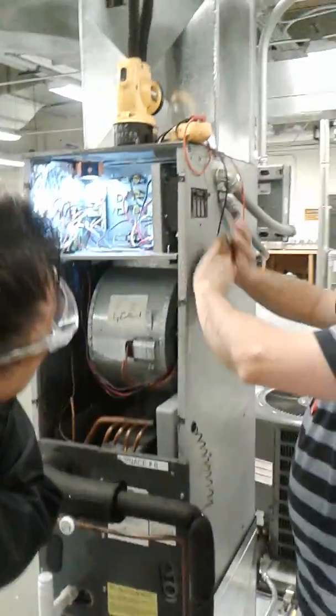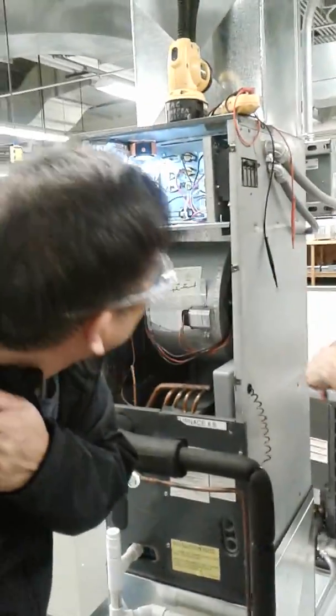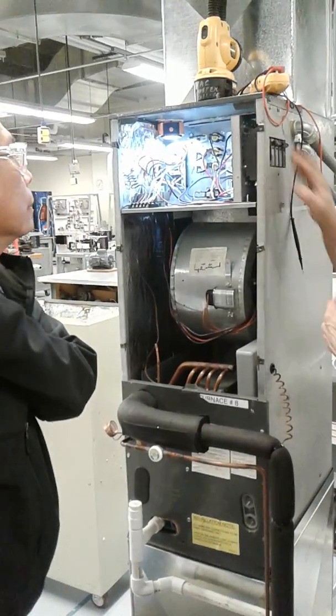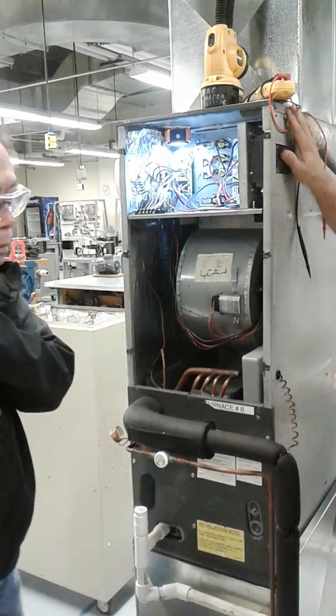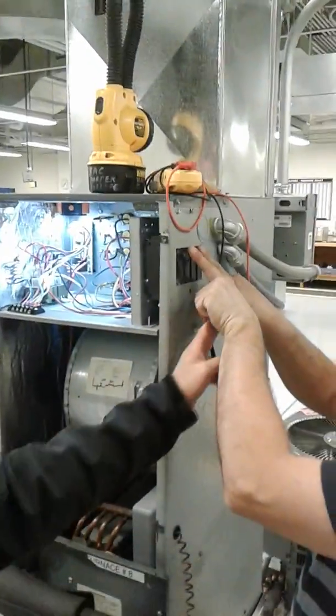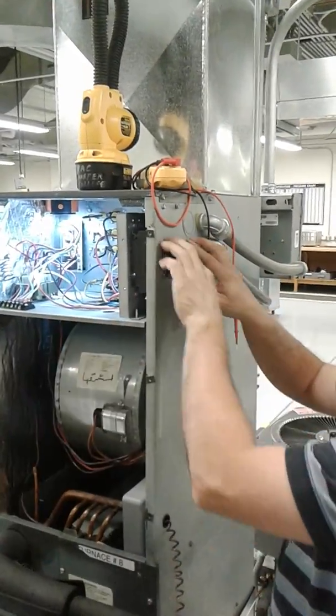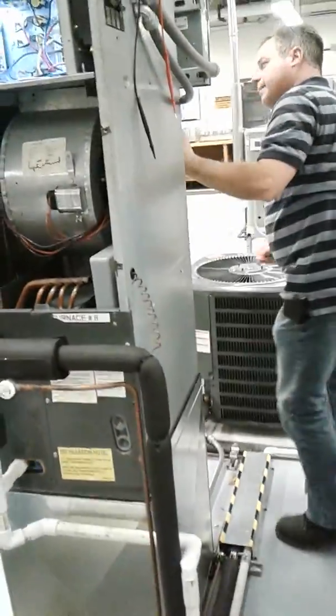Energizes the furnace. That's it. There's no gas valve. There's no other source of power except for the breaker right here. Okay? Two on the side, right? 220, 220. Yes. 2-pole right there. Okay? Now, you need to check the disconnects in the back.